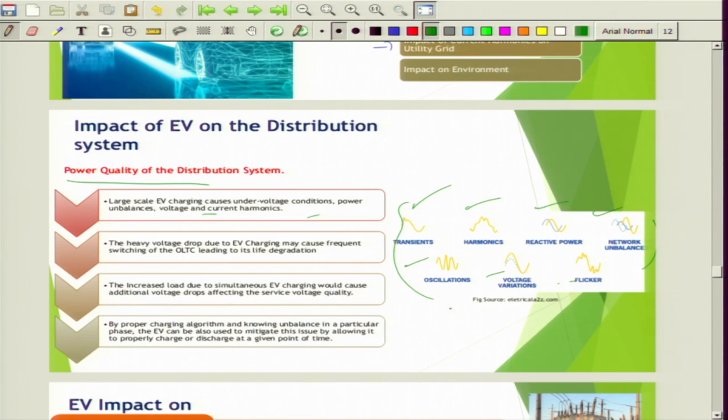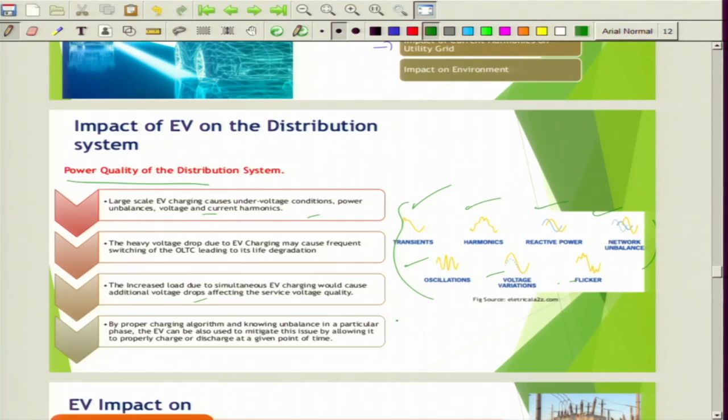If vehicles are continuously charging at a specific distribution transformer, the distribution transformer with tap-changing capability has to frequently adjust the voltage back to the nominal value. This frequent tap-changing operation may hamper the life of a conventional mechanically operated on-load tap-changing transformer. Increased load due to simultaneous EV charging would cause serious voltage drop and power quality issues.